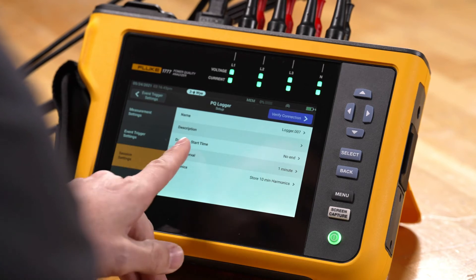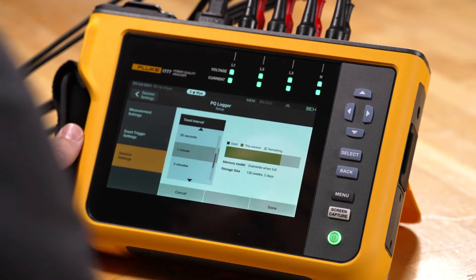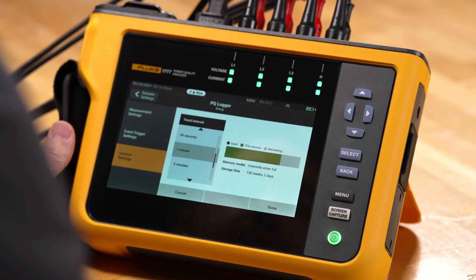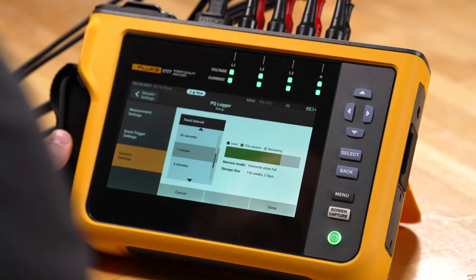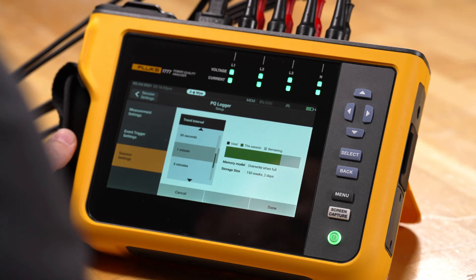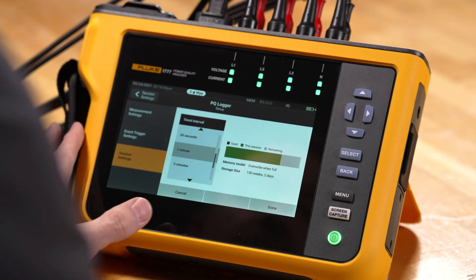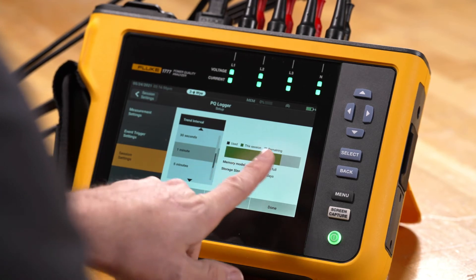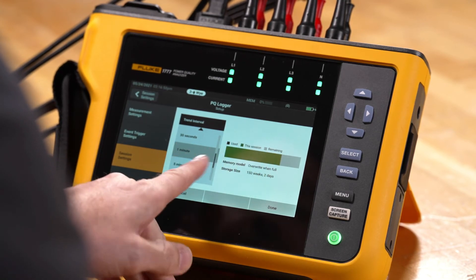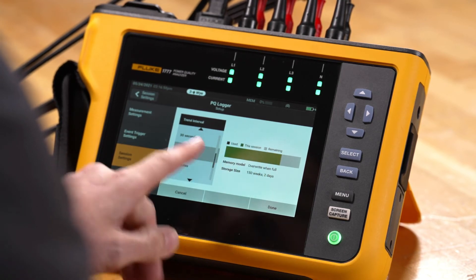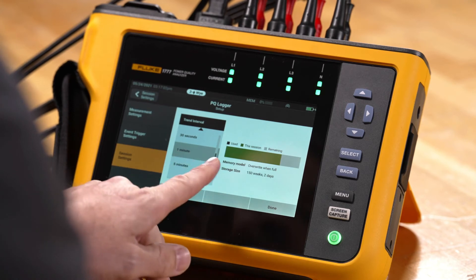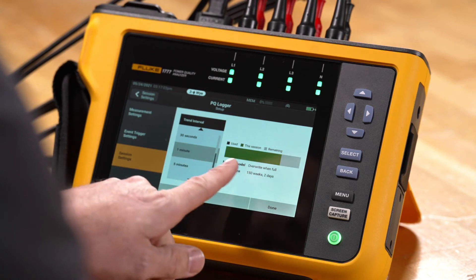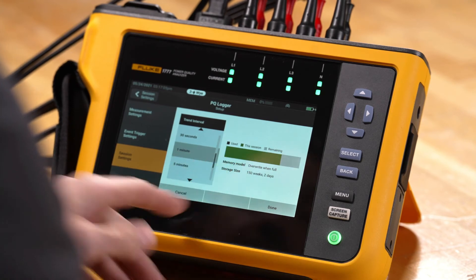We also have trend interval. Trend interval ties into the resolution of the trending data itself, which will be min, max, and average trend data. The trend interval here will be one minute, but we can set it as low as one second, or we can increase the time to extend the length of recording that we have.